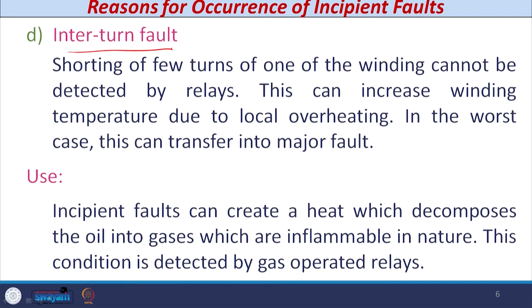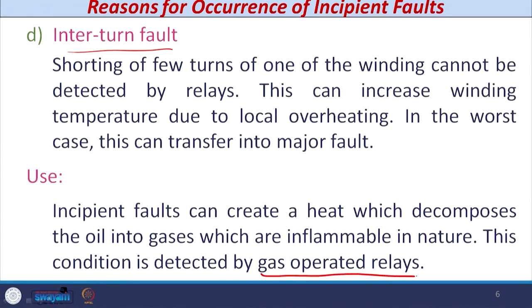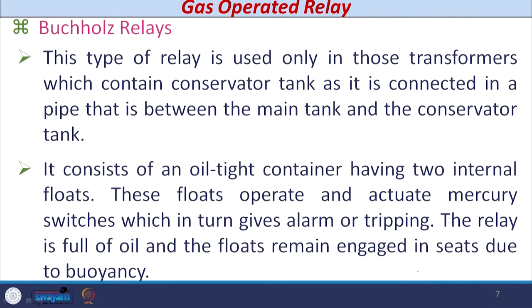Let us see how to detect incipient faults. Whenever incipient faults occur — due to interturn faults, leakage of oil, or other reasons — they produce heat. This heat decomposes the oil into gases, which are inflammable in nature and may create a hazard in the transformer. In actual field practice, this type of incipient fault can be detected by gas-operated relays. There are two types of gas-operated relays: the Buchholz relay and the sudden pressure relay.